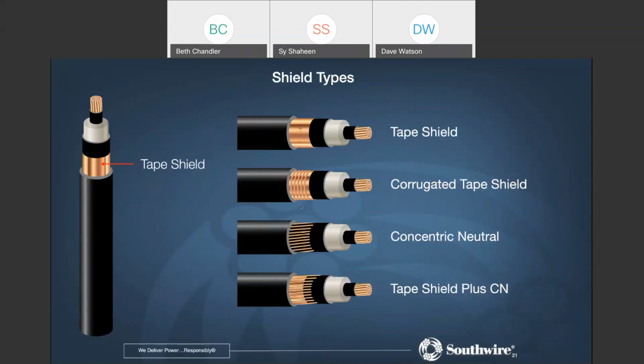There's other shields, what we call a concentric neutral. This is used predominantly in the utility market, whereas this is a hybrid of concentric neutral plus a tape shield. This is a corrugated tape shield. It's just like this, but with a corrugation. But let's concentrate on two of them, this one and this one, just so you can understand the difference. The tape shield is an industrial type of cable used predominantly in the industrial market and in the data centers. Not to say this isn't used in the data centers. We'll get to its applicability in a minute.